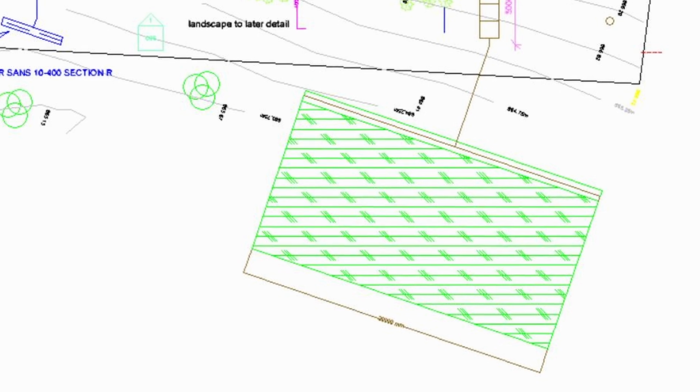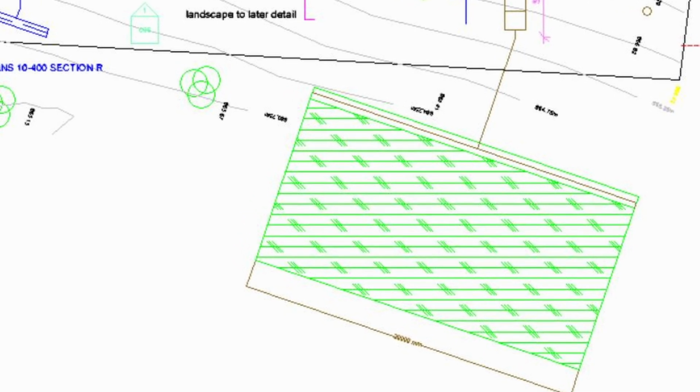Oh, and before I close, the other thing we have to pay attention to is what's called the evapotranspiration area. There has to be sufficient area left aside on your property downstream of the soakaway, where the water flows into the sidewalls, can then migrate downwards into that space, and then evaporation and transpiration from plants takes place. High water demand plants are always much better, but anything will work. You're not allowed to build on that area, and you're not allowed to gravel it or tar it or develop it in any way. No building of swimming pools or anything, so that area has to be set aside.